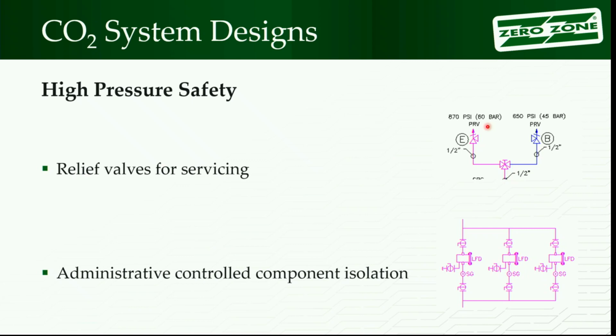So with the system, if I close both of those valves, the liquid filter dryer is going to be what? Full of liquid. So that would put me at a high risk, things start warming up with it. So you have to really pay attention, you don't get distracted and walk away. You know, sometimes you start hearing some noise, sounds like the compressor's crashing at the other end on you. You get a phone call, it's important. You don't just walk away, you got to open one of those valves back up again. Release it back into the system.